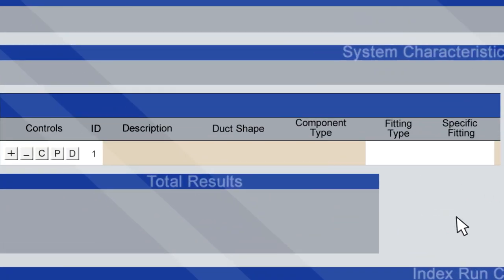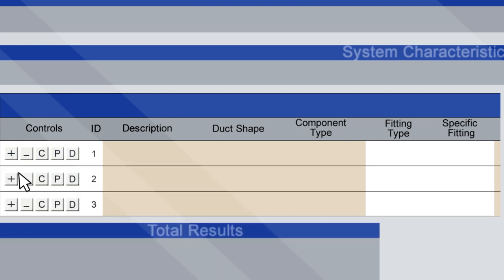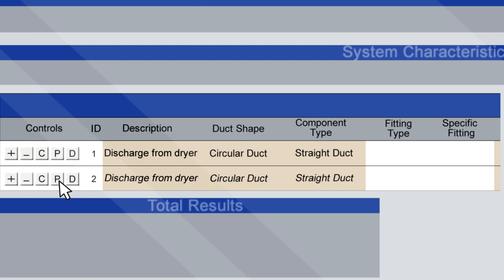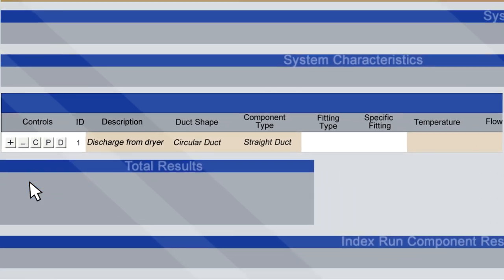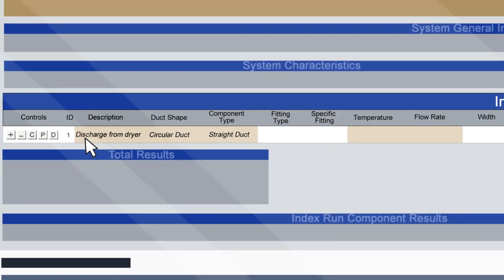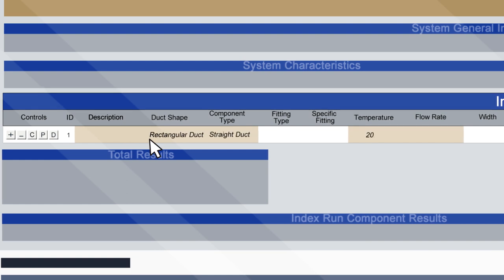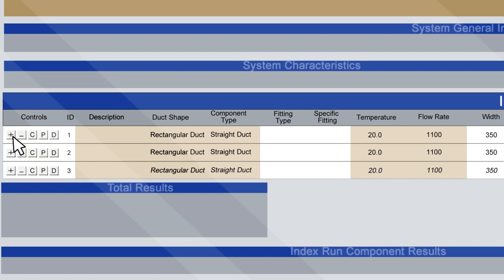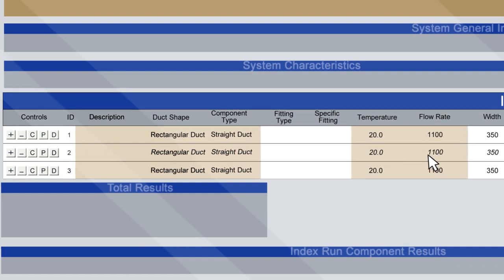Information is entered into the Index Run Details section, one system component per row. It defaults to one row, but more can be added or subtracted using the plus and minus buttons. Rows can also be copied and pasted using the C and P icons. To save time, there's also a button labelled D for default. Enter the most common values used for the duct system, then click the D button to set that row as the default. As you create new rows, this default information will be prefilled, meaning you only need to change properties that differ from the default system.